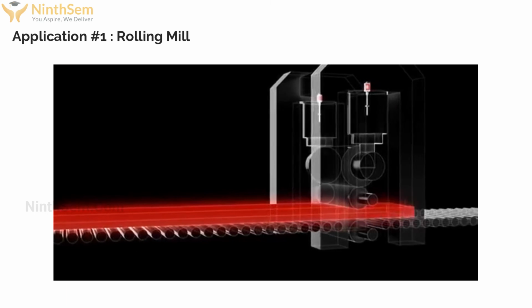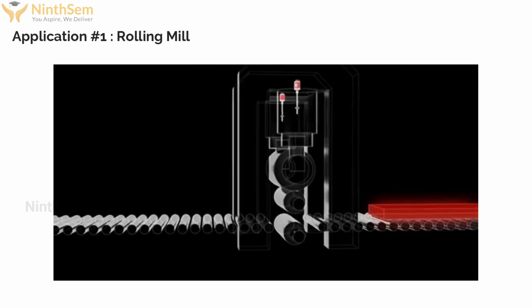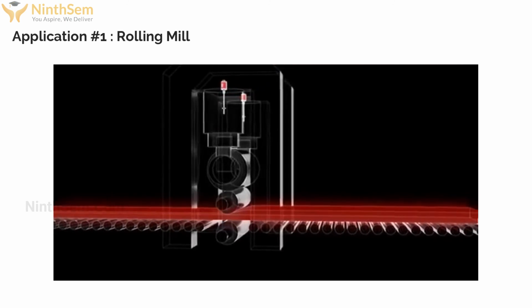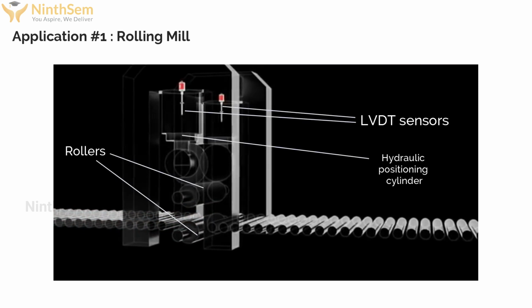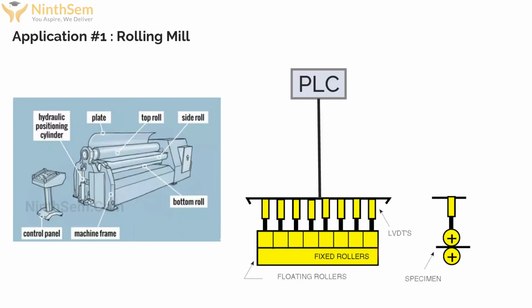Now how is LVDT applied in a rolling mill? As you can understand, a rolling mill is nothing but rolls. Rolling can be done by maintaining the proper roll gap, which can be done by the proper movement of the hydraulic cylinder. So this cylinder position is very important for getting a good rolled product. This position of the cylinder can be maintained by using LVDT, which will give a 4 to 20 milliamp or 0 to 10 volt signal to the PLC, so as to get the proper position of the cylinder. So we can frame a program for automatic operation of the rolling mill. Here generally the LVDT is fed by an AC source, basically 10 volt AC. So this is an application of LVDT in a rolling mill.